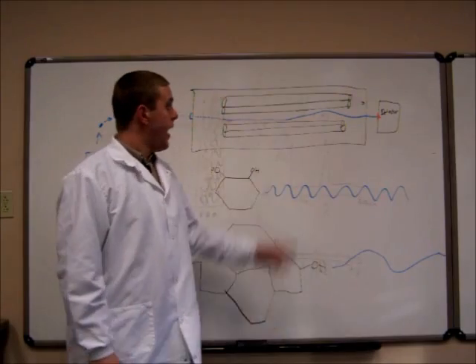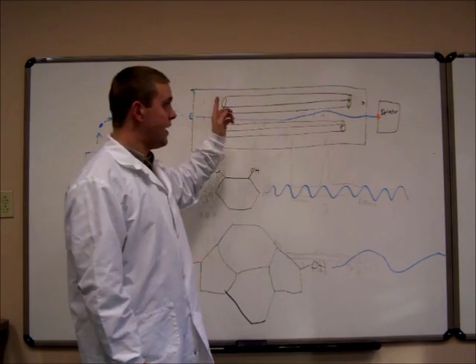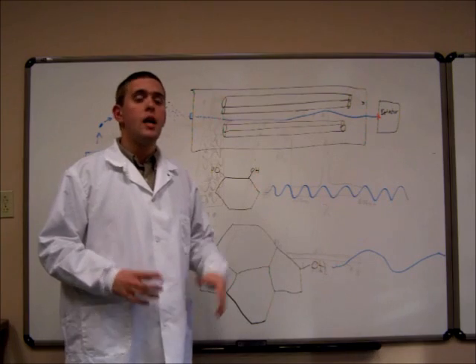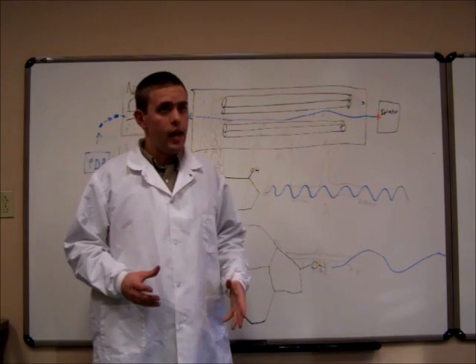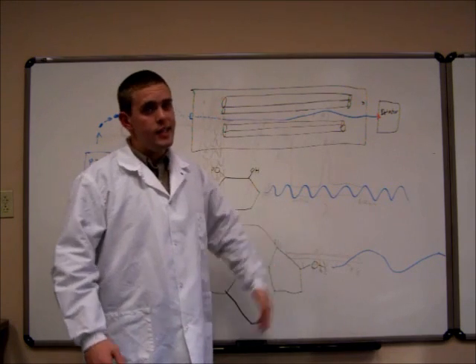Now, keep in mind, everything that runs through the quadrupoles, as I said, if it hits the quadrupoles, it stays there. It's not coming back. The quadrupole is a sealed area that cannot be opened. So if this material hits there, it's never coming back. Now, over many, many years of use, the quadrupole can get a little gunked up.